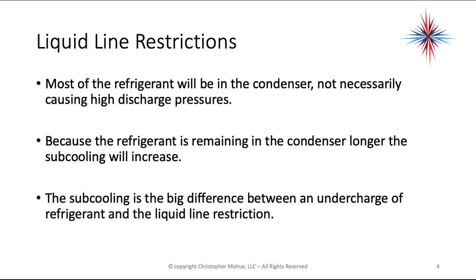Sub-cooling is sensible heat change. The longer the refrigerant is in the condenser exchanging heat with the lower-temperature ambient air, the greater the sub-cooling. Sub-cooling is the big difference between an undercharge of refrigerant and a liquid line restriction. High sub-cooling with the same pressure symptoms as an undercharge indicates a liquid line restriction.